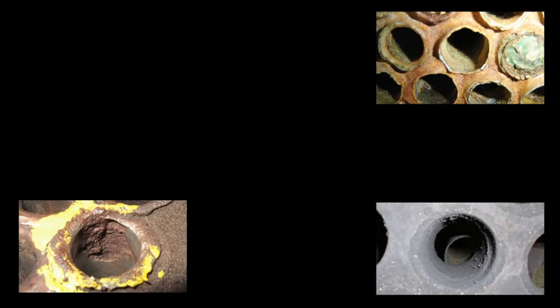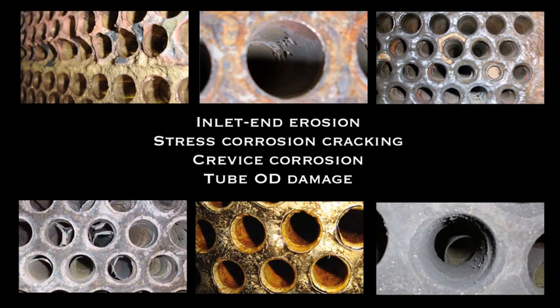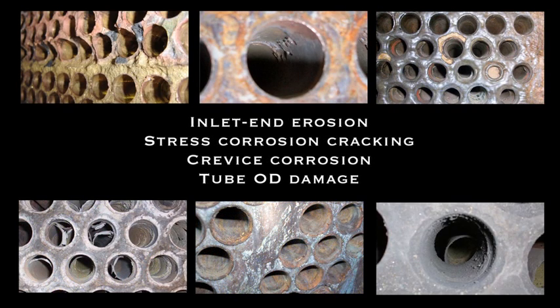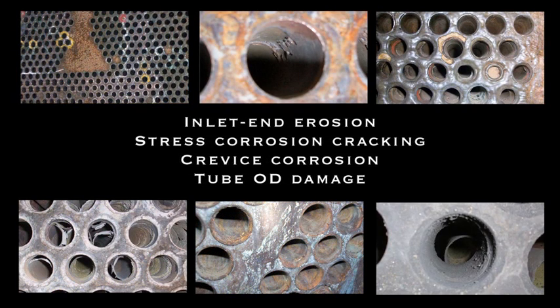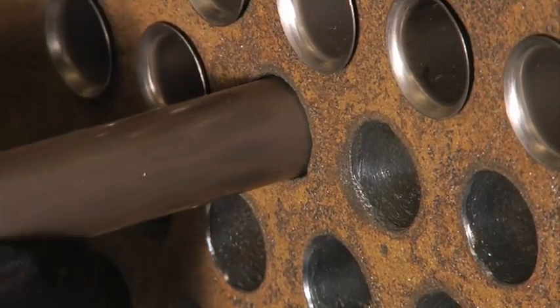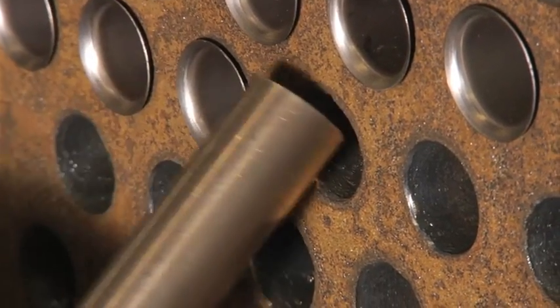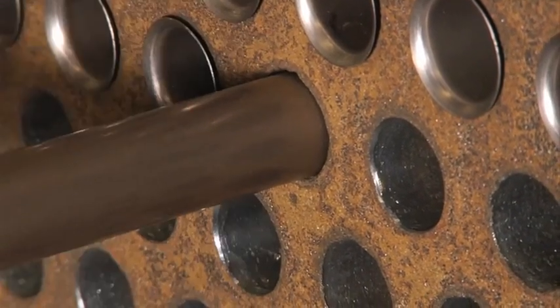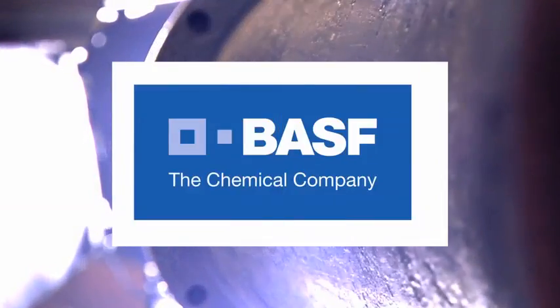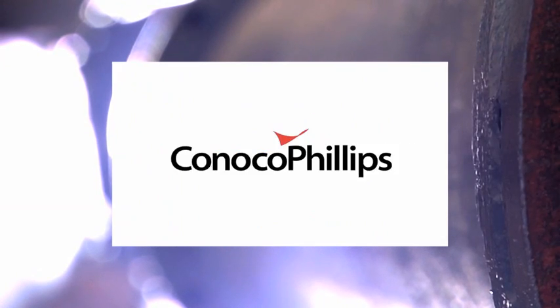Tube end erosion corrosion is the most common cause of tube failure and includes problems such as inlet end erosion, stress corrosion cracking, crevice corrosion and tube OD damage. CTI shields repair these failures and eliminate the need for replacing the entire tube, fixing the problem where the damage occurs. Besides the obvious huge money savings on material, there is reduced labor, equipment and costs associated with downtime.